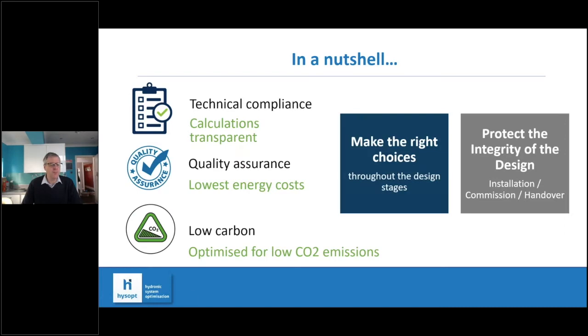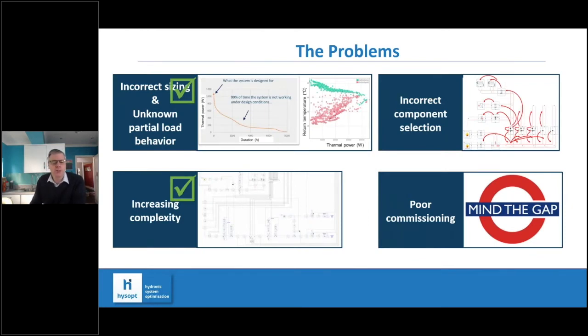The key is also about how you then ensure the integrity of that design at the installation, commissioning, and handover stage. Without going into too much detail, once the design is correct, the software iteratively does all the calculations necessary to select all the pumps and valves in the system based on the correct valve authorities and correct pump heads for the lowest possible energy cost. So it helps with component selection, and it also helps with commissioning, because as part of the same outputs, the installer gets a shopping list of equipment needed for every component, along with the preset commissioning value for those parts. So for every valve, the installer knows what Kv or Kvs value it should be set to, allowing them to pre-commission the system as part of the installation. So not only does it work correctly, it also saves them a lot of time on site.